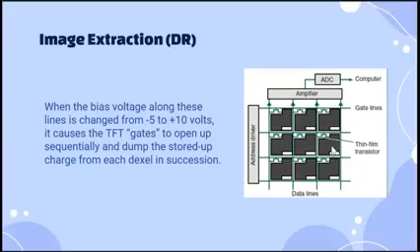Okay, so once enough voltage is stored in the storage capacitor, it causes the TFT gates to open up sequentially and dump the stored up charge from each Dexel in succession.